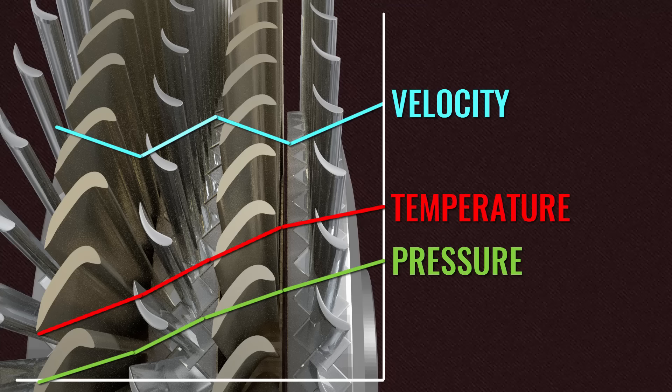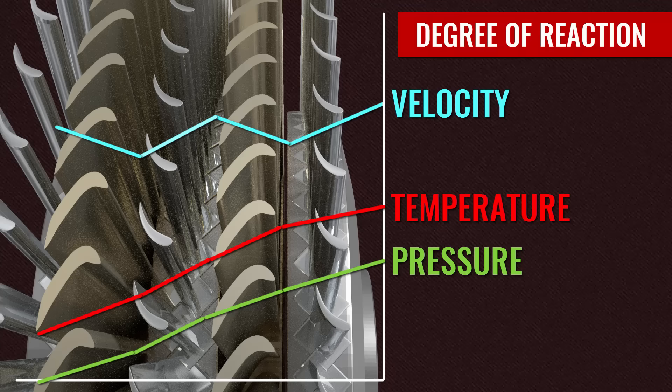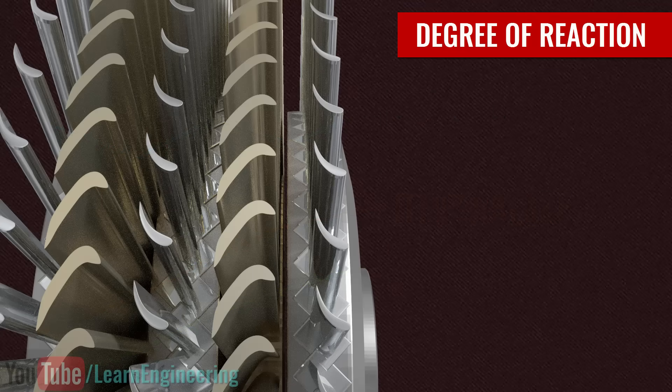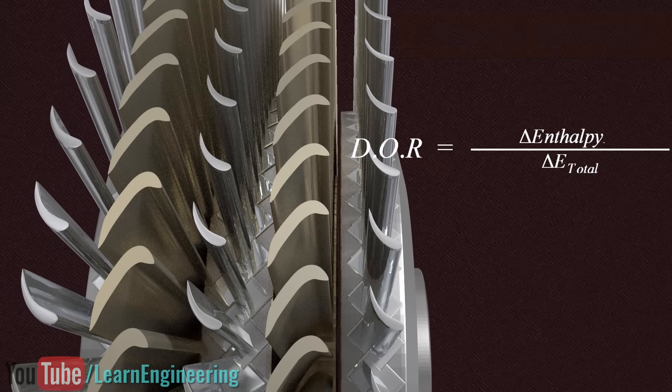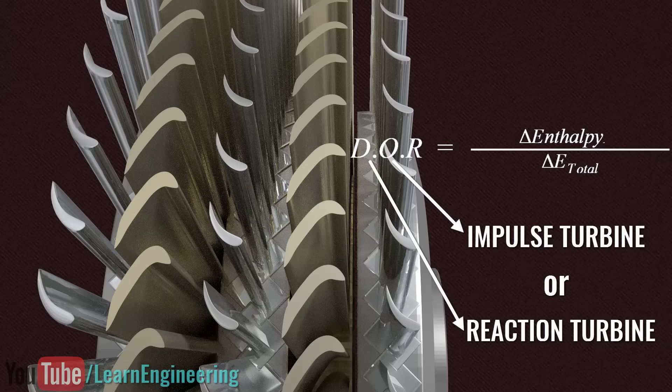There is an important term while designing steam turbines, namely, degree of reaction. This term is calculated by dividing pressure and temperature energy by the total energy change in the rotor. Pressure and temperature energy together is called enthalpy. The degree of reaction decides what type of steam turbine it is.